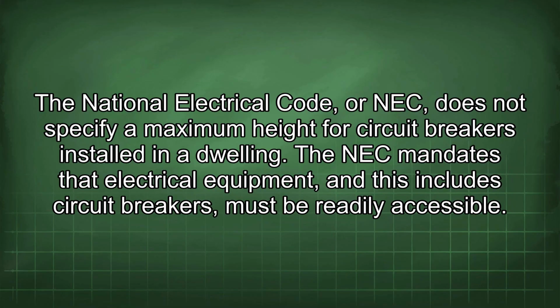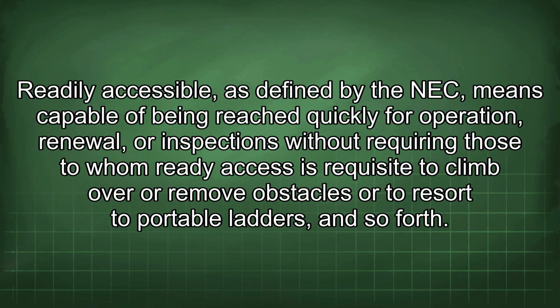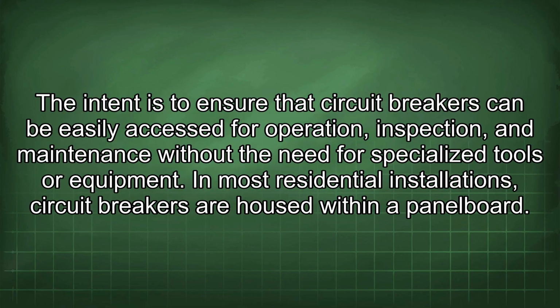The National Electrical Code, or NEC, does not specify a maximum height for circuit breakers installed in a dwelling. The NEC mandates that electrical equipment, and this includes circuit breakers, must be readily accessible. Readily accessible, as defined by the NEC, means capable of being reached quickly for operation, renewal, or inspections without requiring those to whom ready access is requisite to climb over or remove obstacles or to resort to portable ladders, and so forth. The intent is to ensure that circuit breakers can be easily accessed for operation, inspection, and maintenance without the need for specialized tools or equipment.